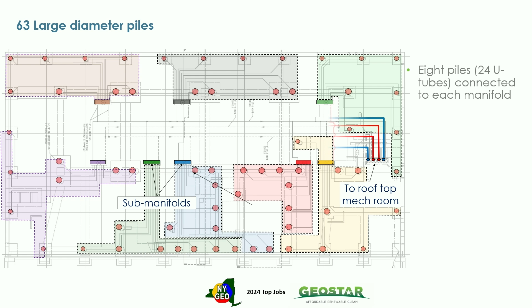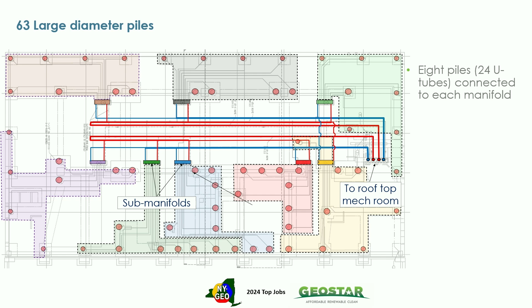But then to add even more resilience to the solution, what we then do is we've got an east circuit and a west circuit. So there was a thought that maybe we could operate one side of the building as a cooling system and the other side as a heating circuit, so when you're delivering heating, you're chucking the cooling into the cooling zone, and then the seasons change and you reverse the system.